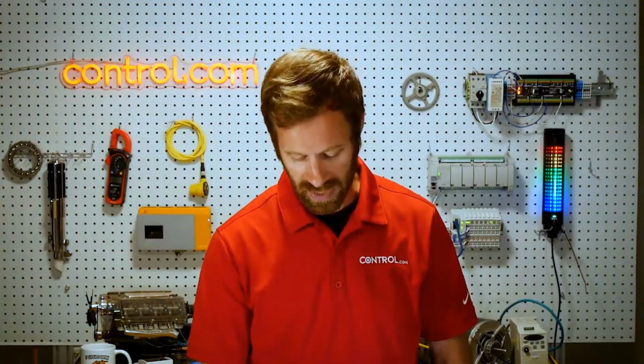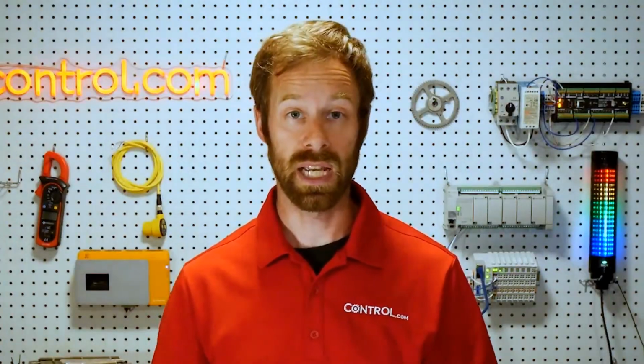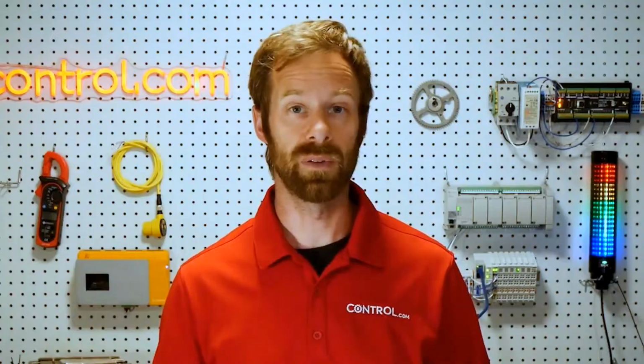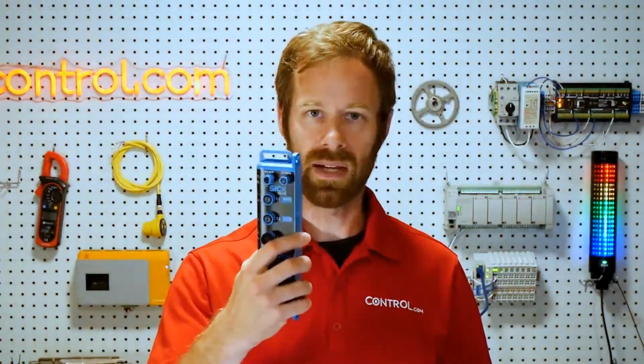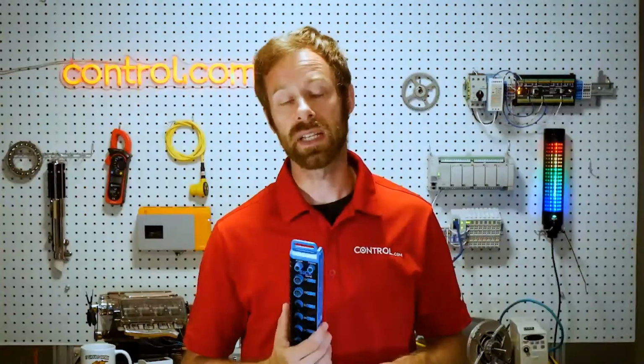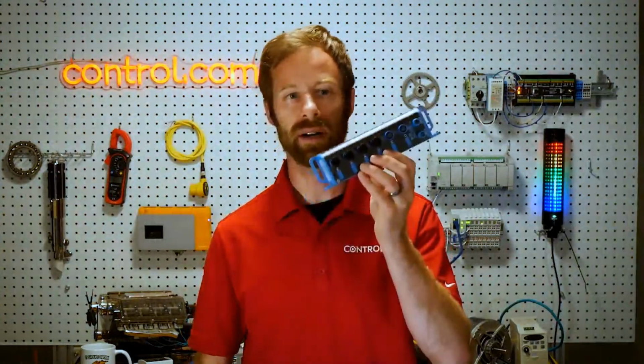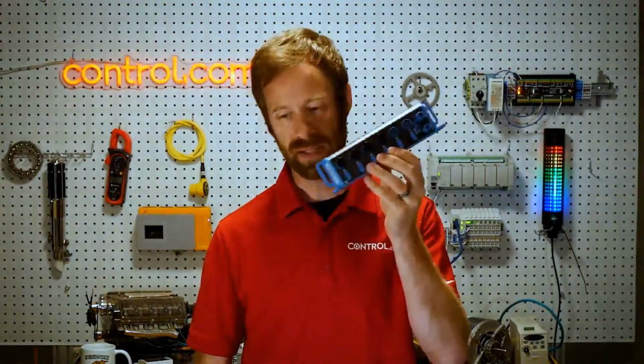We will also then need a communication cable, that field bus cable, Ethernet, Profinet, EtherCAT, to be able to talk between the I/O link master and the PLC. So it does introduce a little bit of extra hardware in this kind of complex, somewhat costly device that goes in between, but the speed with which we can expand a system, change a system, upgrade a system later on is a great way of future-proofing, especially for those kind of systems which are in the design phase right now, the greenfield kind of systems where we could dream.